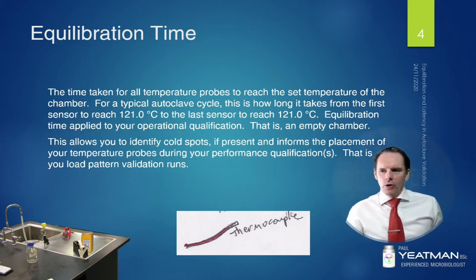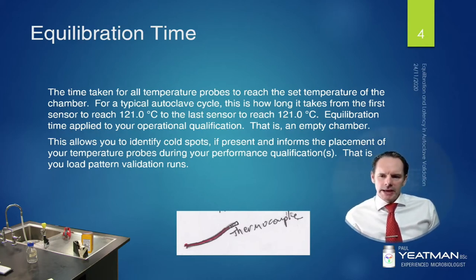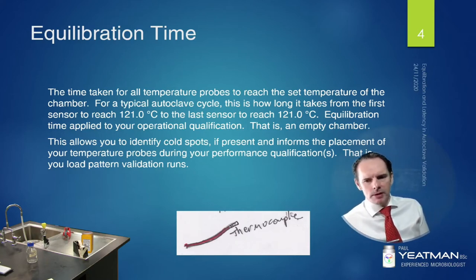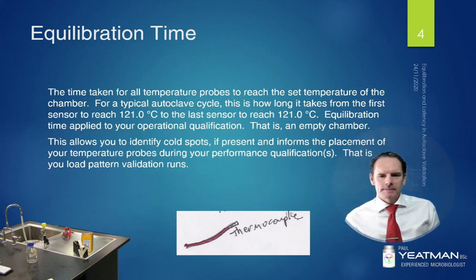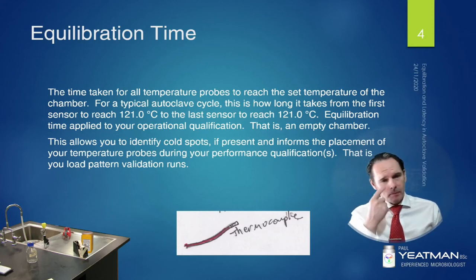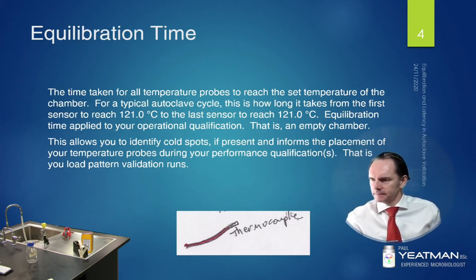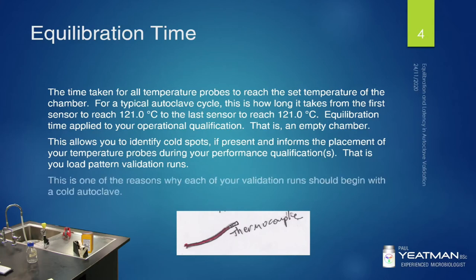By starting your validation cycle with a cold autoclave, the amount of energy needed to heat the chamber is increased — that's part of the thermal load we'll be discussing. This translates into a longer time for your temperature probes to heat up to the required temperature. By determining your equilibration time you'll also be able to identify your cold spots. As part of your PQ, if you do find cold spots, place more probes around the area for more valuable data. This is one of the reasons why each validation run should begin with a cold autoclave — cold autoclave means more energy required to reach the required temperature, so effectively worst case.